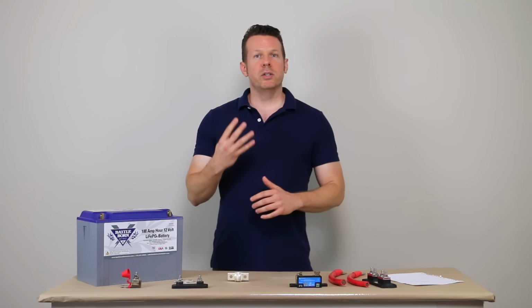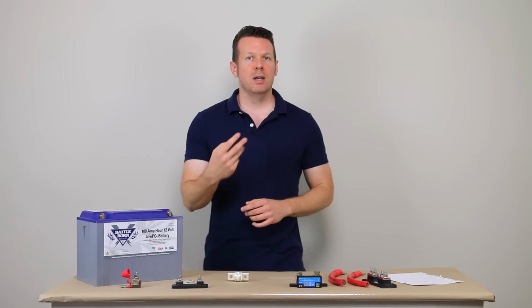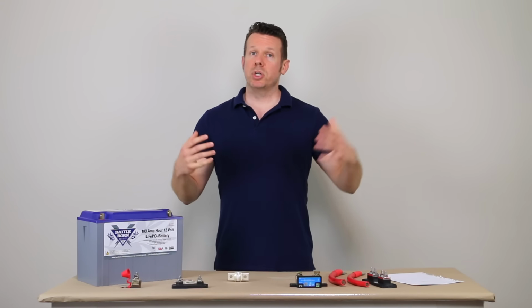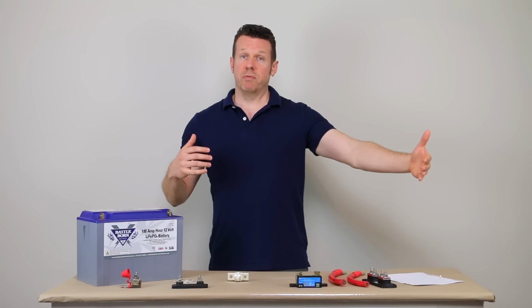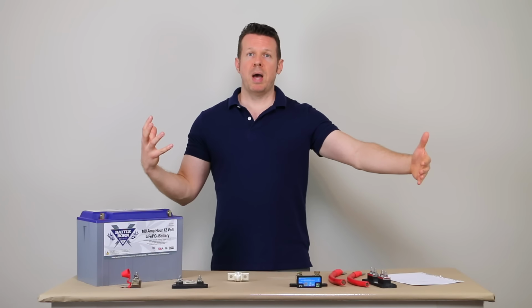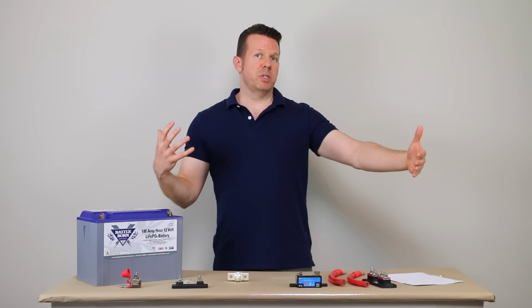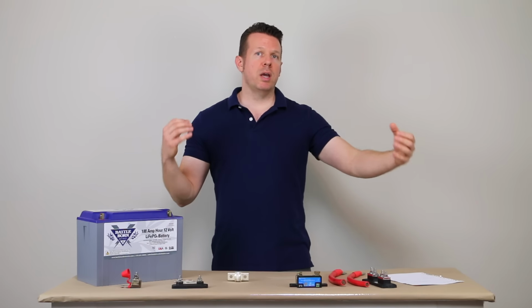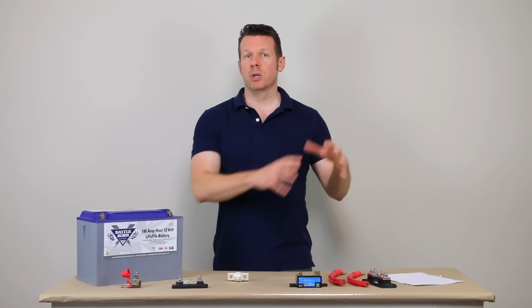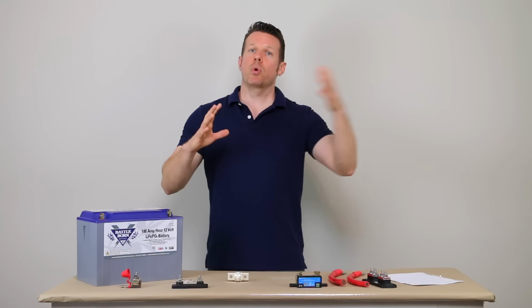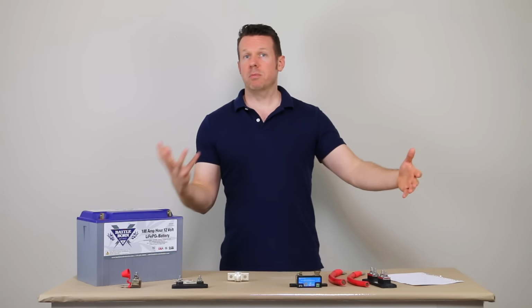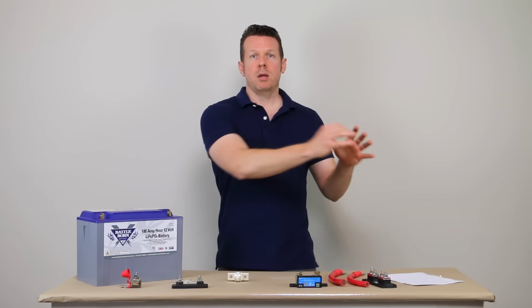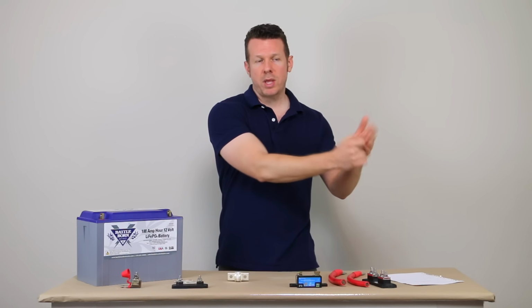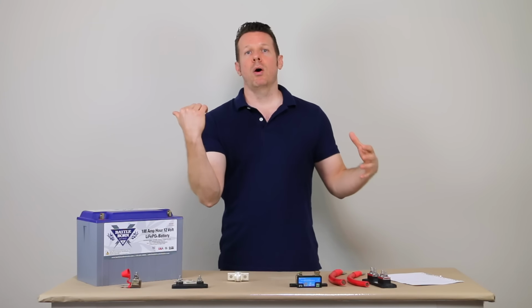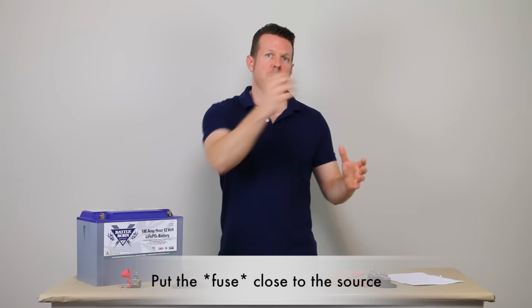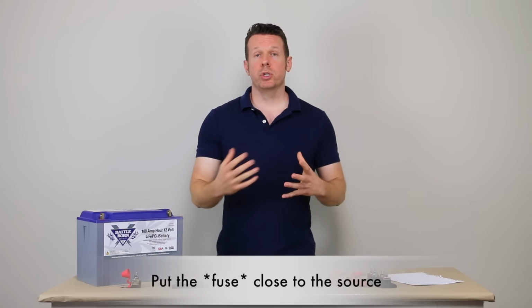Mistake number 4 is no fuse near the battery bank. Going back to the guy I mentioned that had the batteries at the front of the vehicle, the power system was at the back. Oftentimes it's hard to know where these fuses go, and you need a main battery fuse, and you want to put it at the source of the power, not at the power system. You want to put it near battery positive when that cable leaves that battery bank on its way to the rest of the system. Put that fuse close to the source.